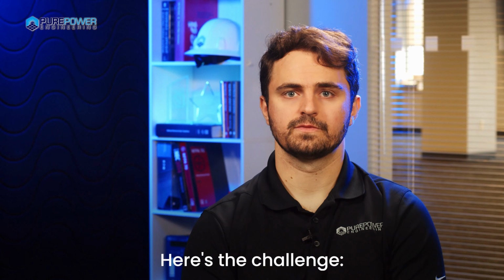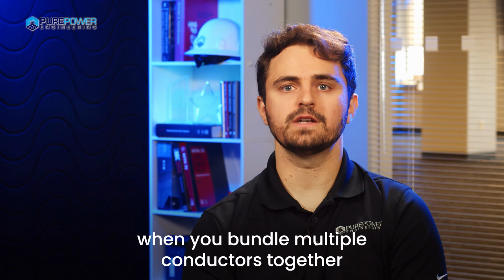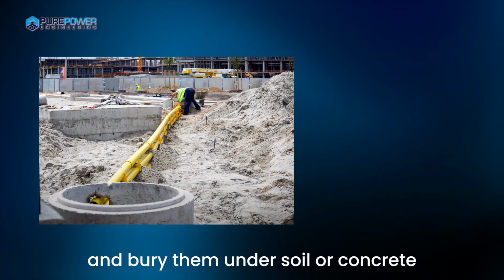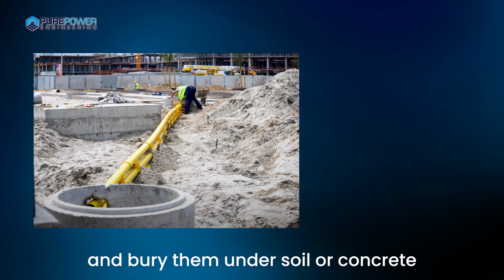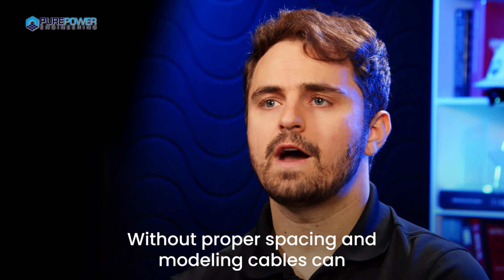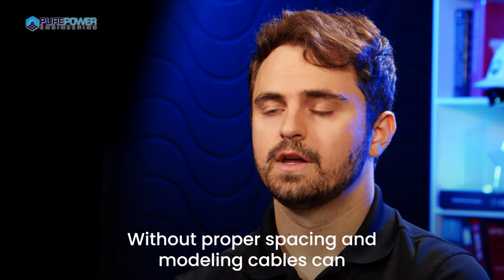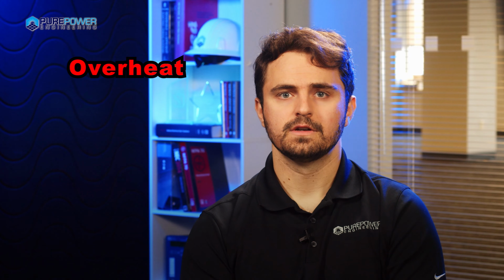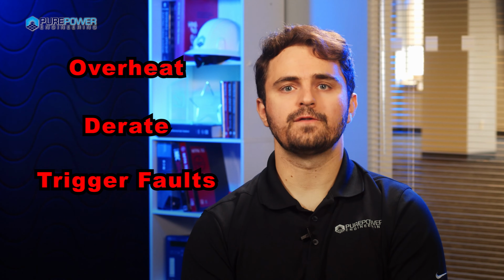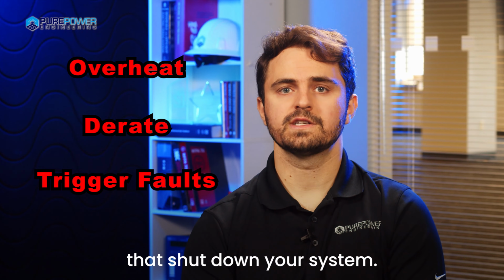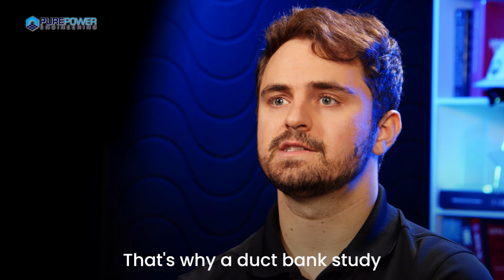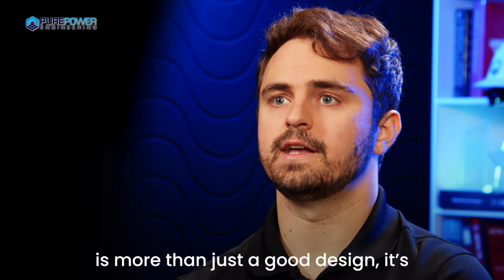Here's the challenge. When you bundle multiple conductors together and bury them under soil or concrete, heat builds up. Without proper spacing and modeling, cables can overheat, derate, or trigger faults that shut down your system. That's why a duct bank study is more than just a good design.